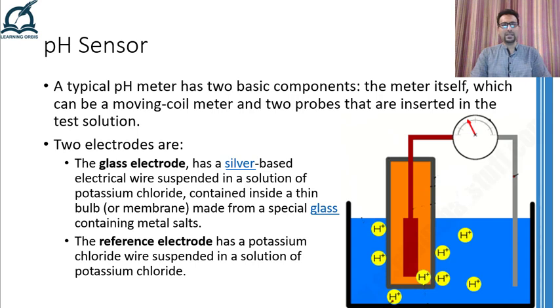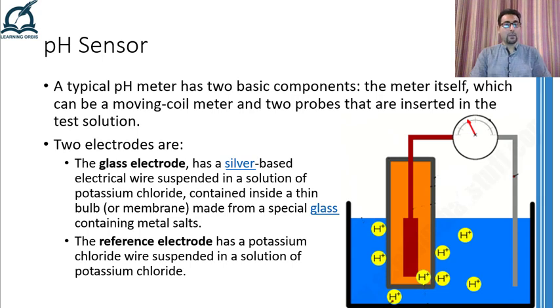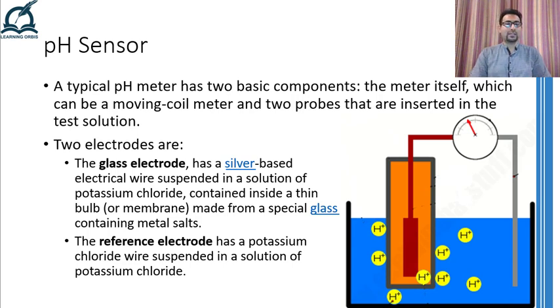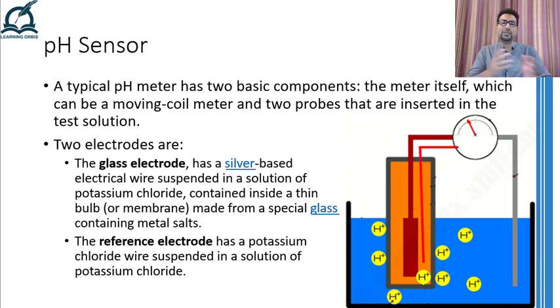So no matter which type of meter you are using, you have to dip the probes in the solution whose pH is to be measured. When the probes are inserted in the solution of unknown pH value, the hydrogen ions present in the test solution replace some of the metal ions on the outside of the glass tube through a process called ion exchange. The same activity will also happen on the inside of the glass tube, where the hydrogen ions in the potassium chloride solution will replace some metal ions on the inside of the glass tube. Now if the test solution is acidic, more ion swapping will occur on the outside as compared to the inside, whereas in case of an alkaline solution, more hydrogen ions will replace metal ions on the inside as compared to the outside.